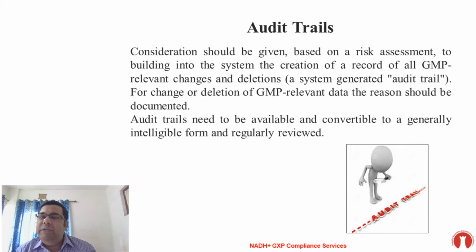Okay. The next question is: what is the recommended retention period for electronic data? Basically, there is no guideline for the electronic data retention period. In 21 CFR, they have specified that yes, you can remove the data if the backup is taken. Some type of clause is given, either in the 21 CFR or in the question and answer session of the 21 CFR. But inspectors are raising concerns on it. So there is no firm guideline at this moment.